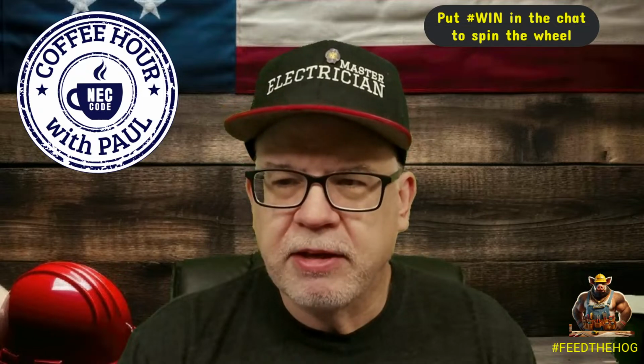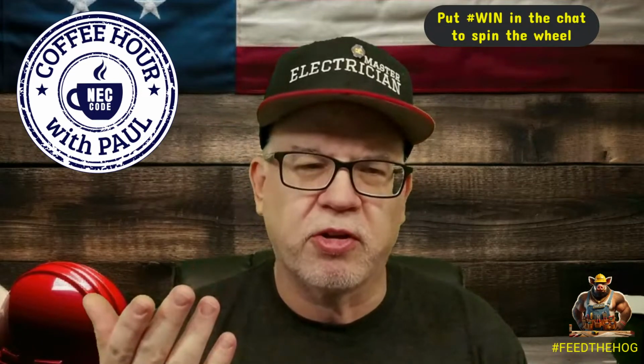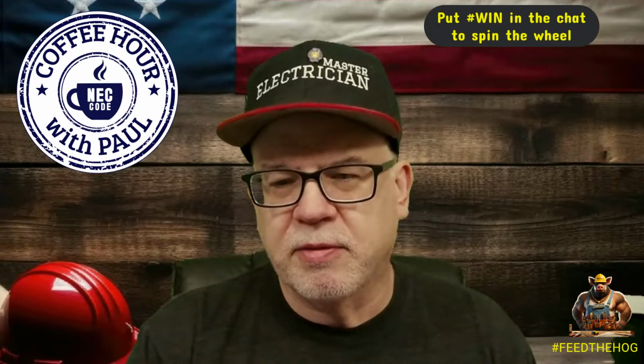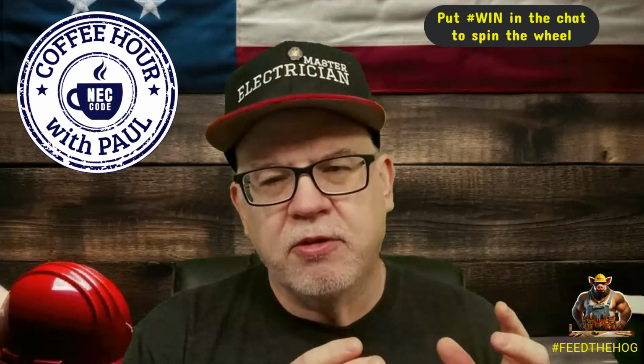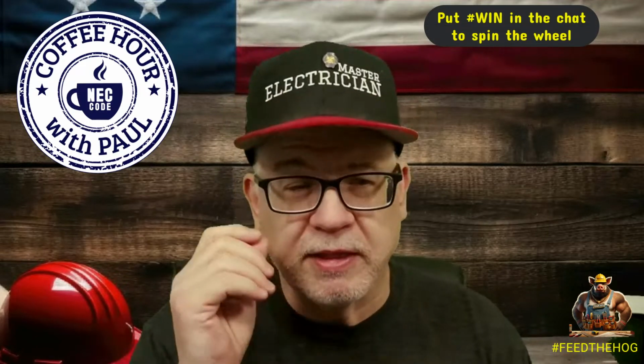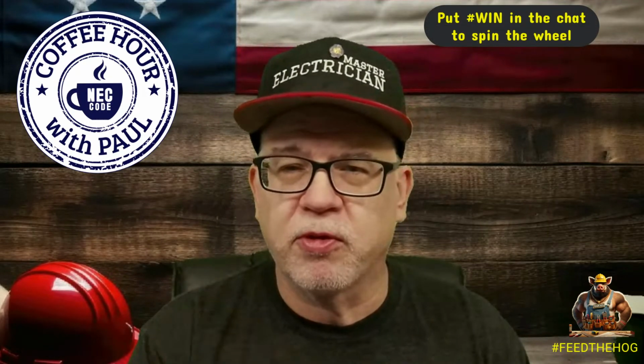And today we're going to get into the same calculation. We're going to get into a bit of redundancy in case you have any questions from yesterday. Maybe you've done some homework and done some calculations, and you saw how it was different from the standard method versus the optional method. We saw the difference between a 1,000 amp rated service versus an 800.